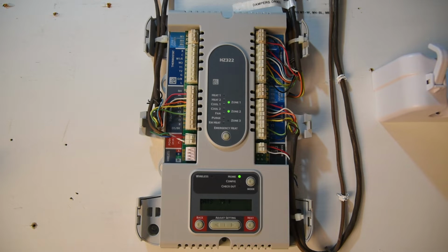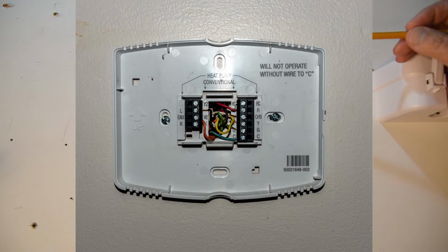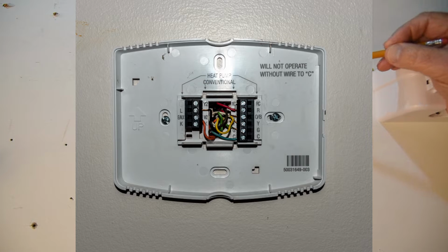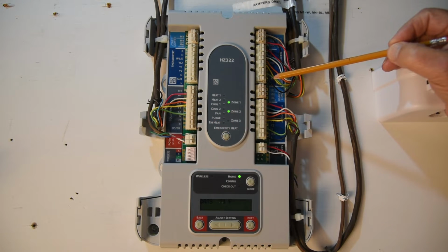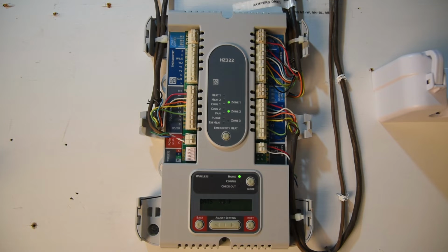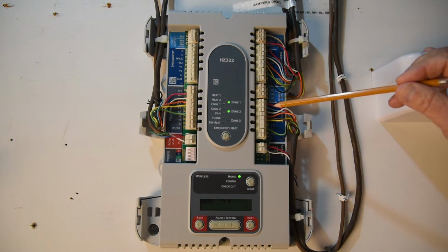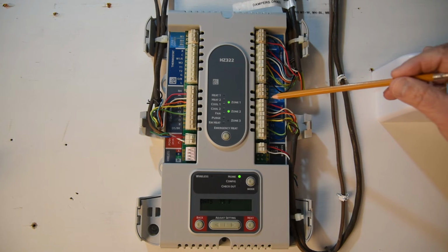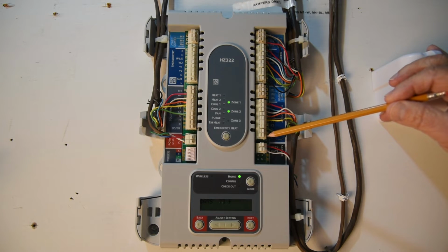What you're going to want to do, when you go to wire it, is take a picture so you can identify all the wire colors and how they've been put on the thermostat. Then as you bring that down, you want to use the corresponding terminals down here. And then for adding a thermostat to your second floor, or wherever you're trying to make changes, you're going to wire that thermostat the same and make the same connections down here.